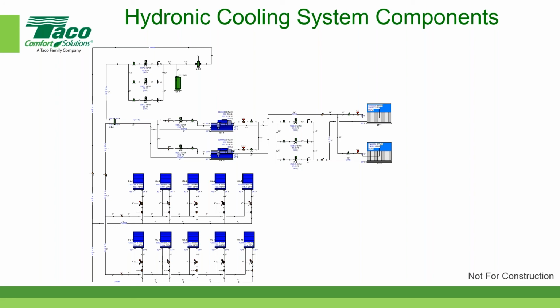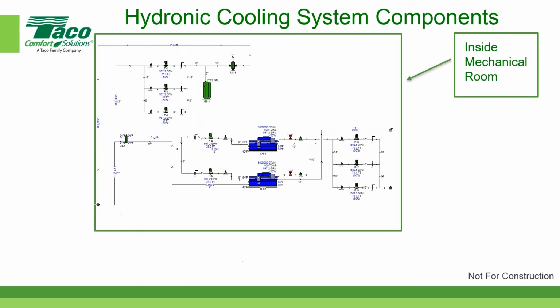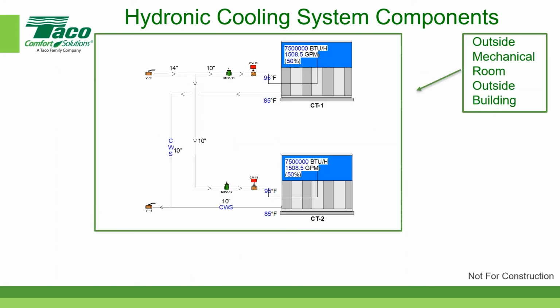So there's no glycol added to the system, but to keep the piping from freezing and to keep the base of the cooling tower from freezing, they use basin heaters in the basin of the cooling tower, and typically, for piping that's exposed to the weather, it's heat traced and insulated. And that has been kind of the standard approach for condenser water systems that have cooling towers sitting out in the weather. So here's our cooling towers. So there would be basin heaters.